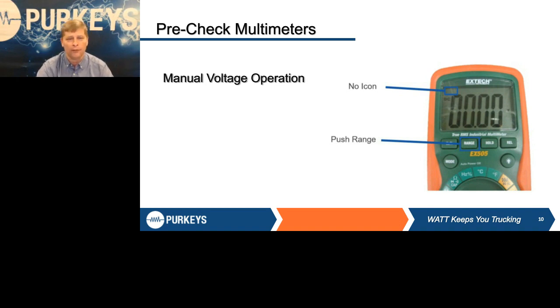No. You definitely want to buy quality leads if you do have to buy replacements. There are some good, let's say, generic-named leads that are still very good. You want to make sure you buy quality leads that have the right ratings, and one of the biggest things is make sure they have the right flexible wire on them. Otherwise, I've seen those be a lot more prone to breakage, and that's where you get a lot of inaccurate readings, because the leads will actually break inside the insulation. So you do want to make sure you're using quality replacement leads if you have to buy them.